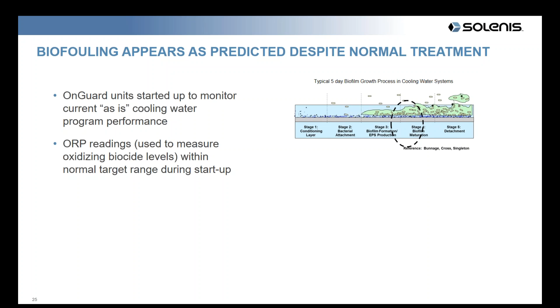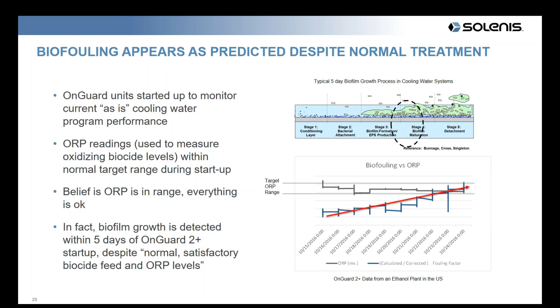But as 2 to 3 to 4 days go by, this is what we typically see: biofilm starting to grow in the OnGuard unit, replicating what's going on in the system. We're also clearly seeing a heat transfer efficiency loss as a result, despite normal biocide and ORP levels, which is typically considered a key operating indicator. The assumption is that if your key operating indicators are in range, you're probably fine. This is one of the things we're seeing that is quite common.